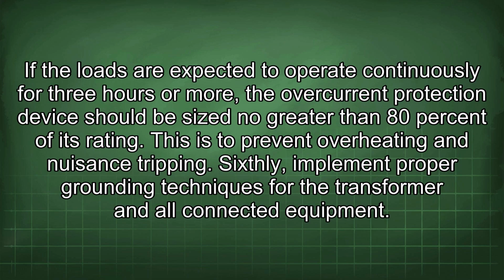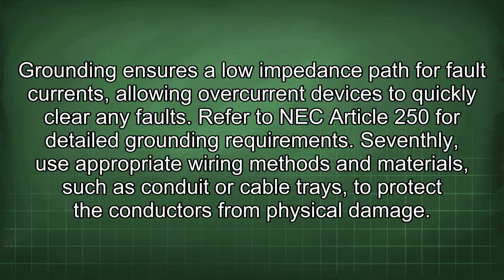If the loads are expected to operate continuously for 3 hours or more, the overcurrent protection device should be sized no greater than 80% of its rating. This is to prevent overheating and nuisance tripping. Sixthly, implement proper grounding techniques for the transformer and all connected equipment. Grounding ensures a low impedance path for fault currents, allowing overcurrent devices to quickly clear any faults. Refer to NEC Article 250 for detailed grounding requirements.